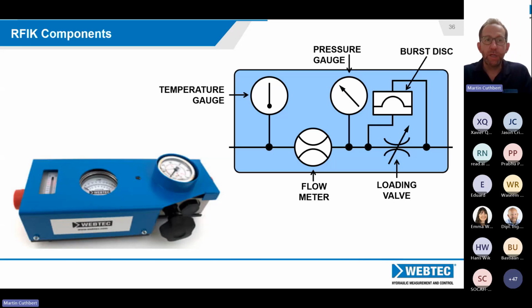So if we were just to open up the tester, if you like, and look at its own hydraulic circuit, you can see there that from left to right, we've got the flow coming in, we've got a pressure gauge teed off it, with the oil going through the flow meter, got a temperature gauge and a pressure gauge teed off, and then the oil goes through the load valve, and then in parallel with that, we've got a burst disc. The advantage of that is that when that burst disc breaks, that's a sort of safety system, the oil is bypassed past the load valve at low pressure, and the oil stays inside the circuit. So it's a safe and flexible solution.